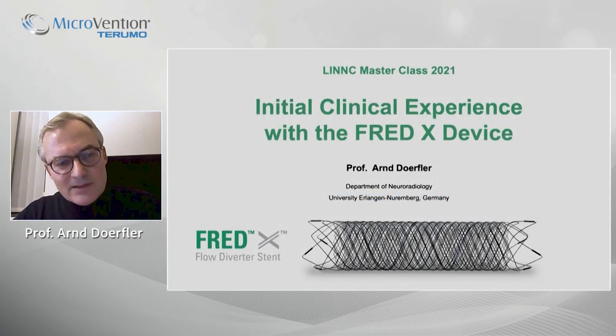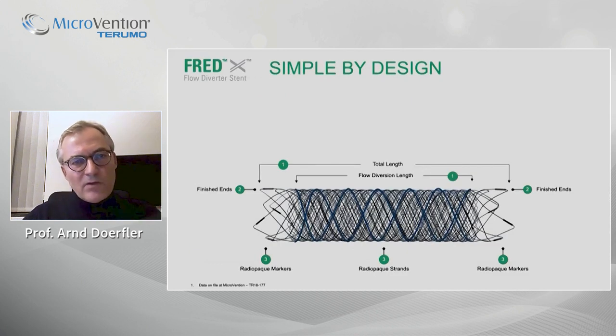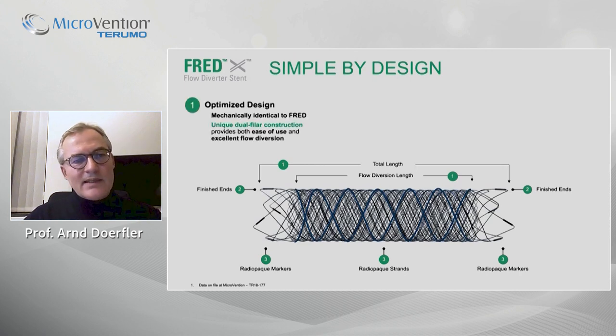Dear colleagues, I would like to present our initial clinical experience with a new FRED-X device. Let us quickly start with a view on the design of the stent. The FRED-X is mechanically identical to the FRED flow diverter with an optimized design and a unique dual filar construction providing both ease of use and an excellent flow diverting effect.